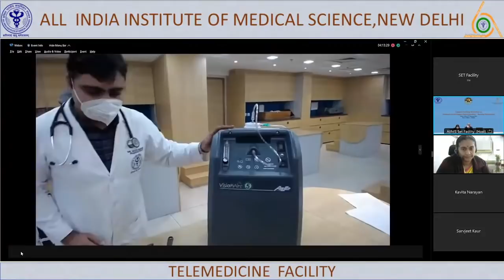I'll be demonstrating the oxygen concentrator. The oxygen concentrator uses atmospheric air. Atmospheric air is sucked in from this inlet port, and in this there are zeolite crystals which absorb the nitrogen, and then the oxygen, which is around 90 to 95% concentrated, comes out through this oxygen outlet. Briefly, I'll tell you about the controls on the machine.